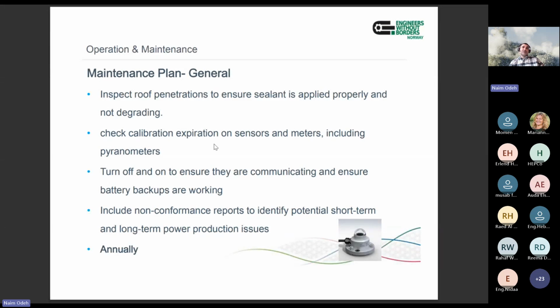This includes the sensors. Most power plants, especially the big ones, have a weather station that continuously records the radiation, wind speed, and others. So it is important to check that they are functioning well, to check that they are clean, and also to check if the calibration certificates are still valid.